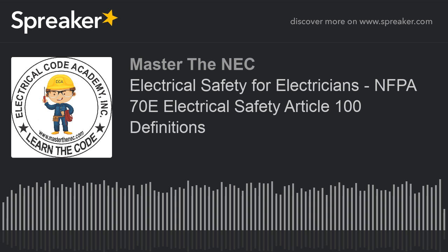What does that mean? I can identify a hazard, I can identify a risk condition, and I can also identify how to mitigate that risk or how to reduce the risk by lockout, tagout, by proper PPE, by all of these conditions. I'm reducing the associated risk. And in many cases, eliminating the risk, okay, by using de-energized practices. The point is, are you qualified? If you've never worked on a switchgear, but you're an electrician, are you qualified?